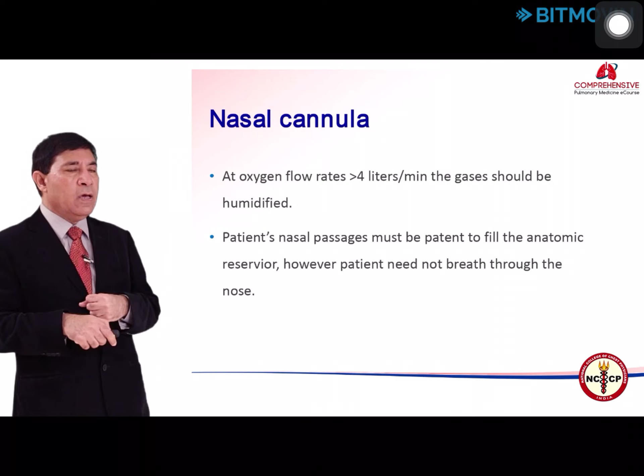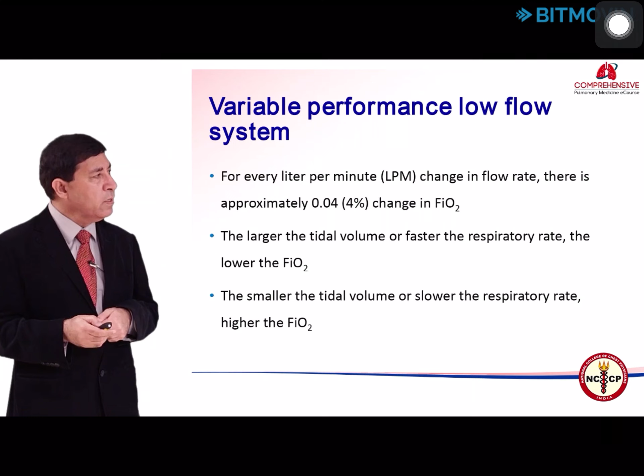Roughly, if the patient's breathing pattern is constant and the patient is breathing less than 25 cycles per minute, then for each liter there is a change of 4%. So if the tidal volume is smaller and the breathing is slower, the FiO2 can be higher for a given flow rate. On the other hand, if the tidal volume is larger and or the breathing rate is faster, then for the given flow rate, the FiO2 can be lower.